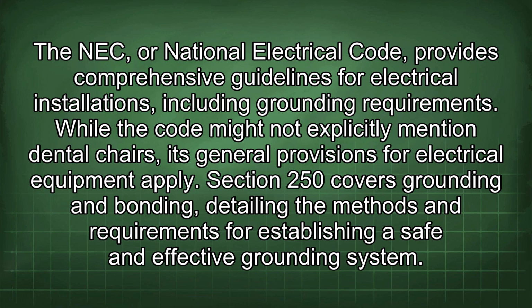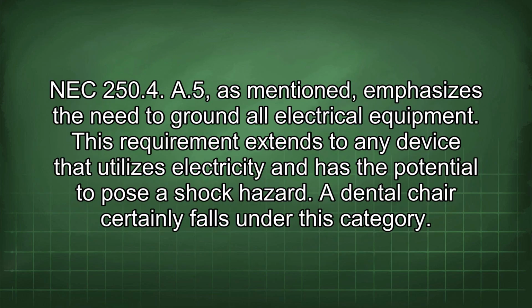While the code might not explicitly mention dental chairs, its general provisions for electrical equipment apply. Section 250 covers grounding and bonding, detailing the methods and requirements for establishing a safe and effective grounding system. NEC 250.4(A)(5), as mentioned, emphasizes the need to ground all electrical equipment. This requirement extends to any device that utilizes electricity and has the potential to pose a shock hazard. A dental chair certainly falls under this category.